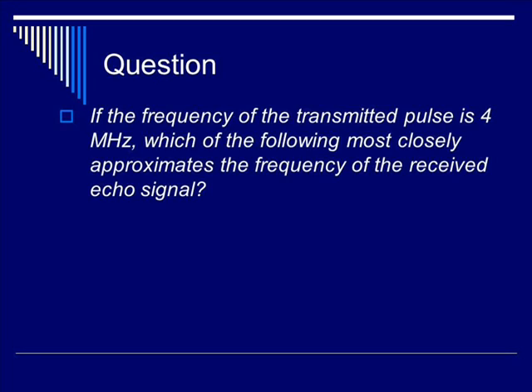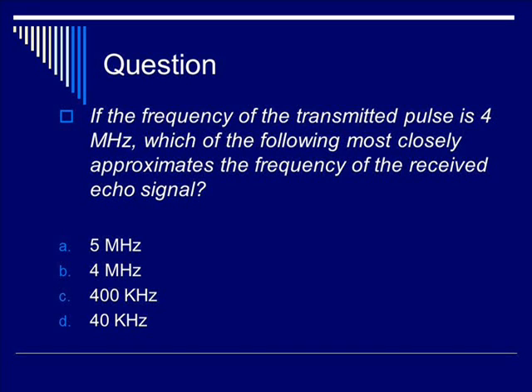Let's test your knowledge. If the frequency of the transmitted pulse is 4 MHz, which of the following most closely approximates the frequency of the received signal? Is it A, 5 MHz? Is it B, 4 MHz? Is it C, 400 kHz? Or is it D, 40 kHz? The correct answer is B — 4 MHz. As discussed earlier, the transmitted and received frequencies are very close in a Doppler system.